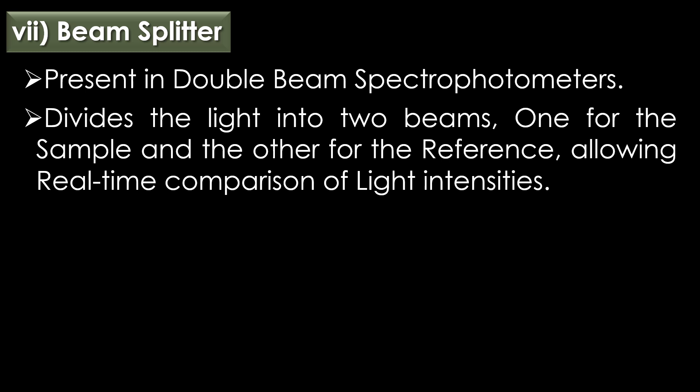Beam splitter: the beam splitter is present in double beam spectrophotometers. It divides the light into two beams — one for the sample and the other for the reference — allowing real-time comparison of light intensities.